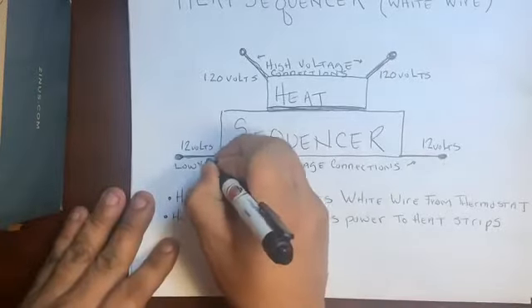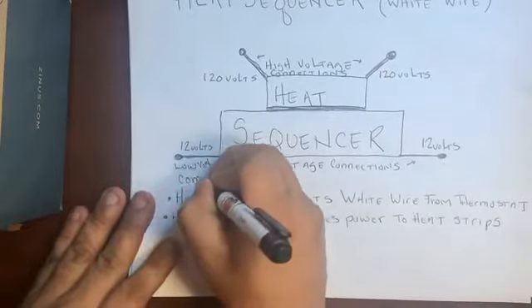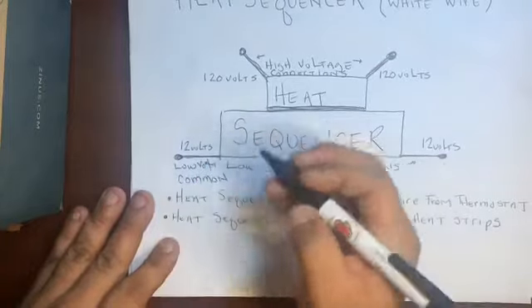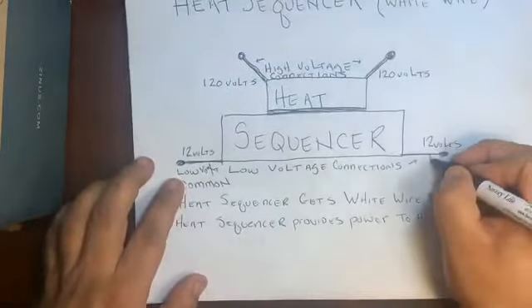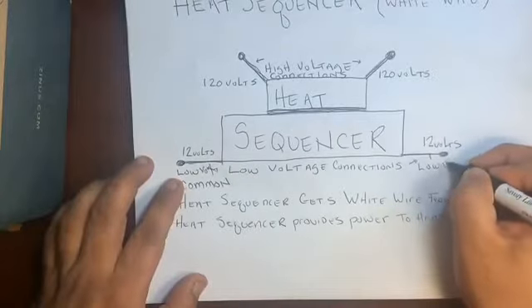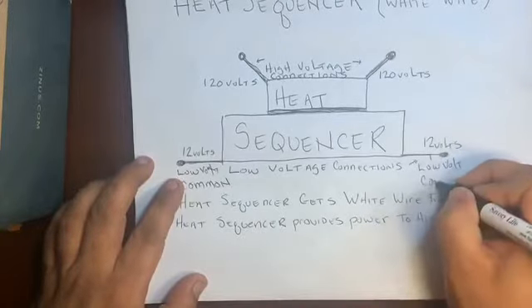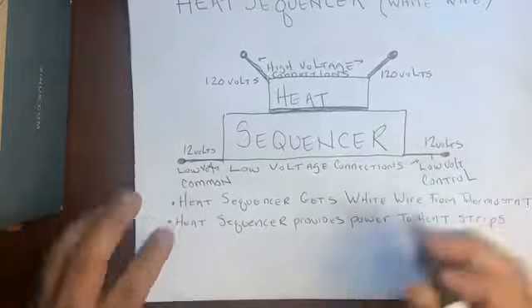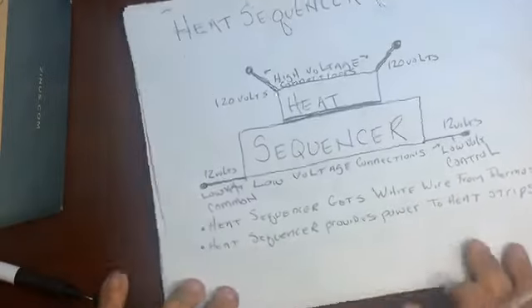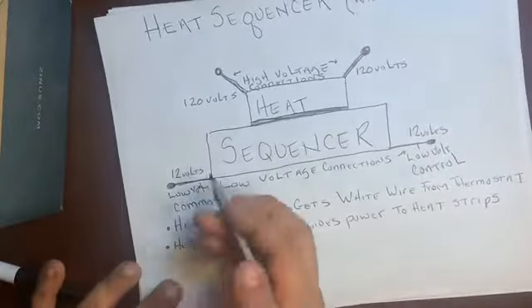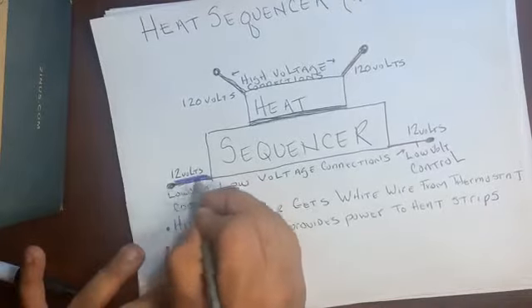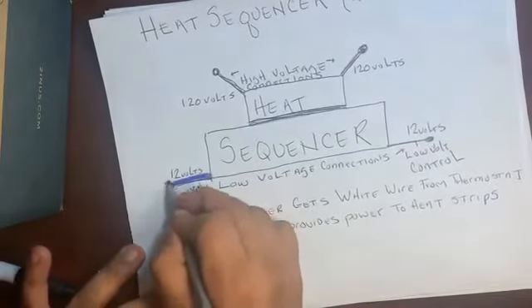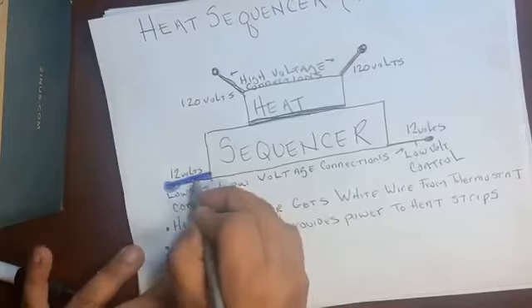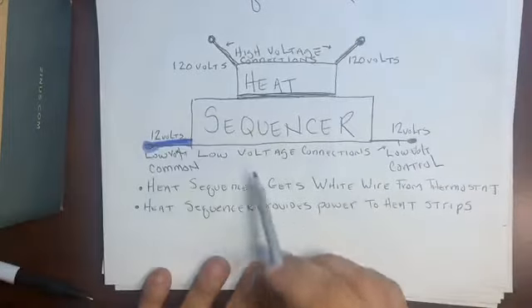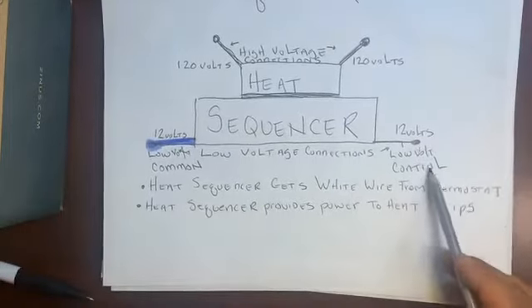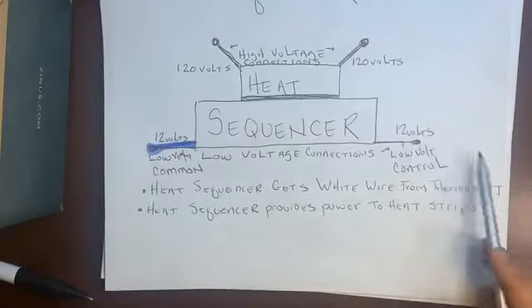Low voltage common. So if this is our low voltage common, then obviously the other one has to be low voltage control. We talked about colors. We'll get a blue out. We know that this heat sequencer will have half of its low voltage is going to get a blue wire. A blue wire. That means that the other side of the 12 volts is the control. And this is what goes to the thermostat.